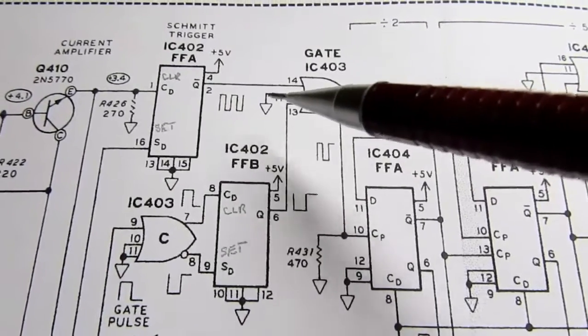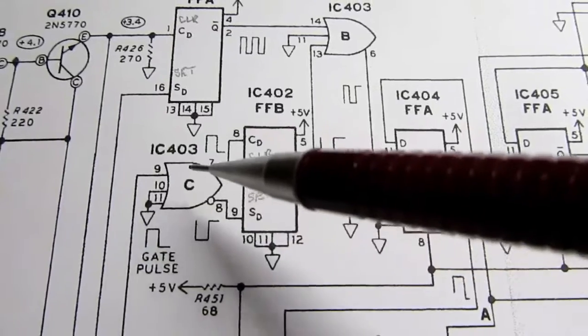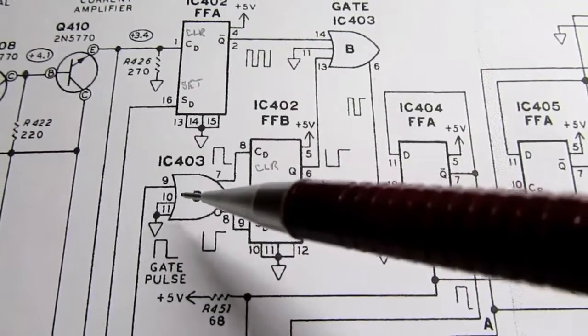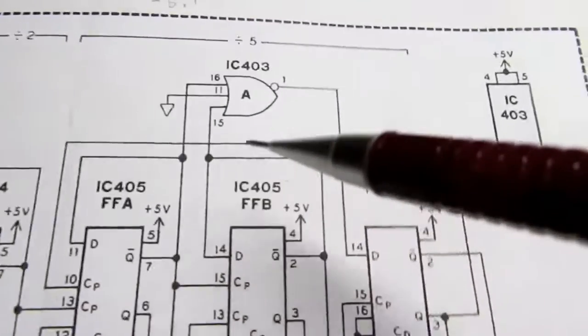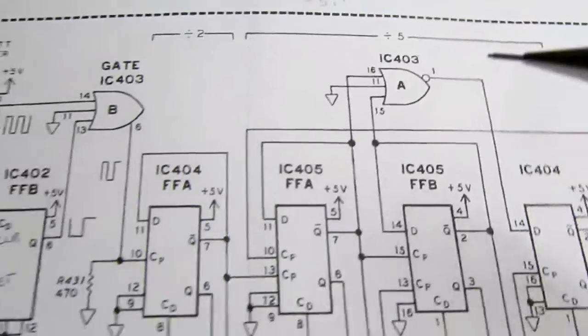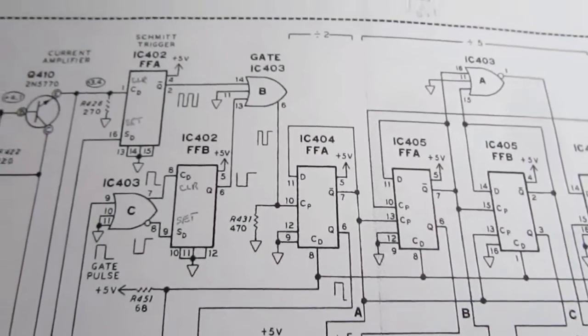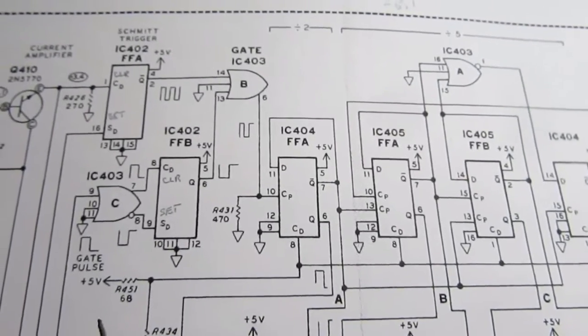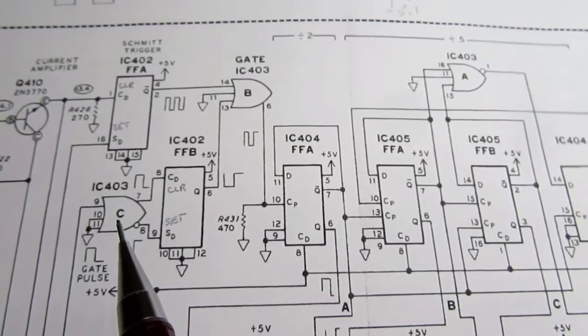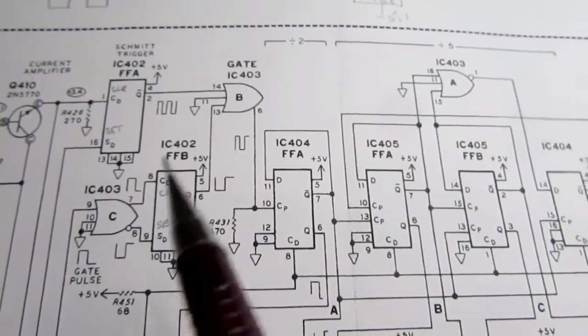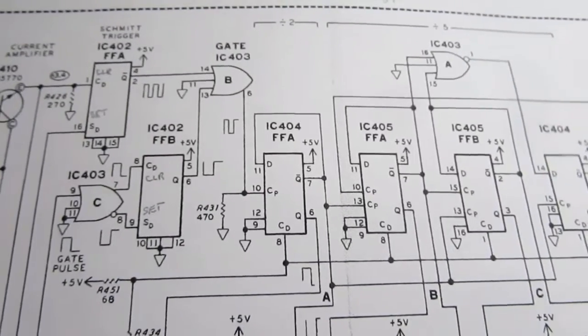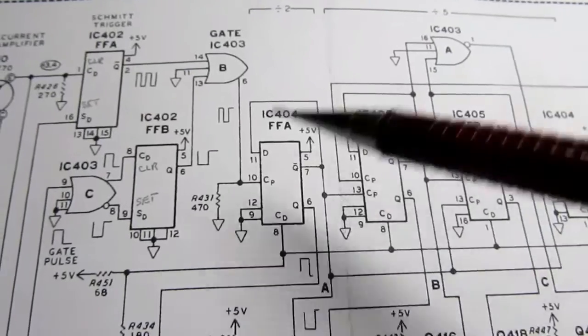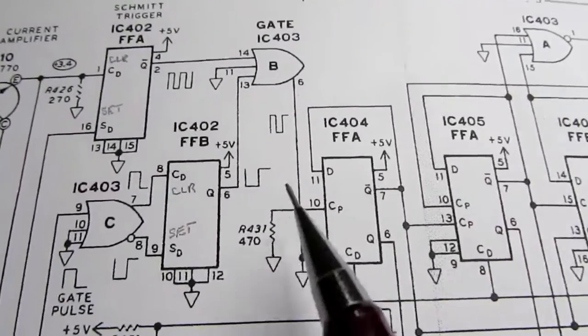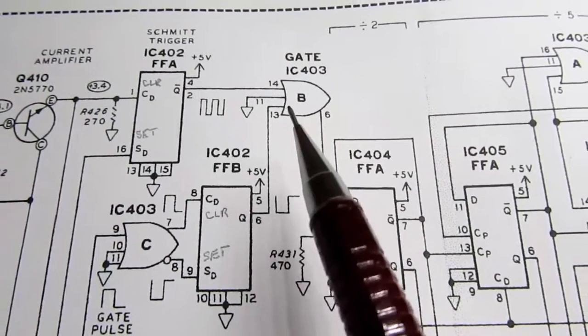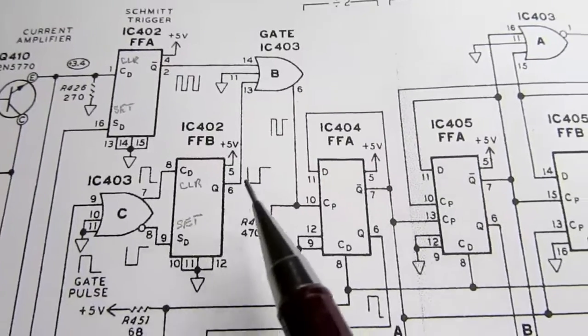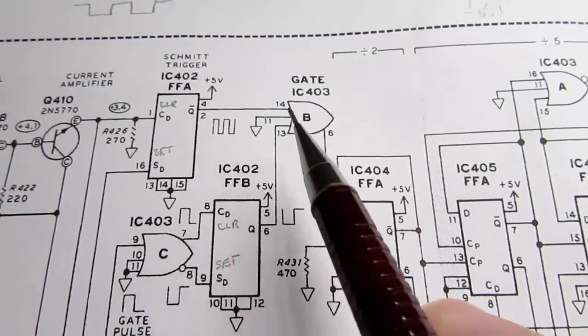This pin 11 that's shown here is going to ground, and here's another incidence of the same IC. It has 3 OR gates in it. What that really is, is a chip enable. So you can disable all 3 OR gates with an enable signal. As long as you have that enable signal pulled low, then the OR gates are allowed to operate normally. And if you pull it high, then they don't work anymore. Well, they're all tied to ground, so that means they're all going to work. That makes this into a 2-input OR gate, and it has this signal, which is the gate pulse, and then it has this signal, which is the input frequency.